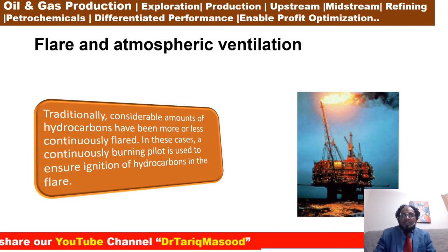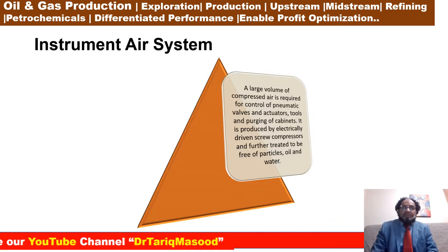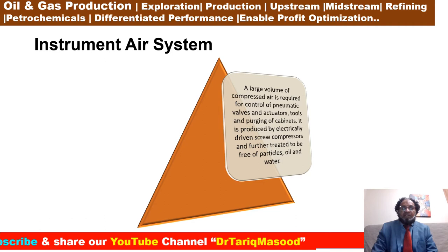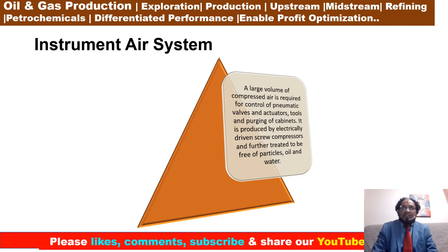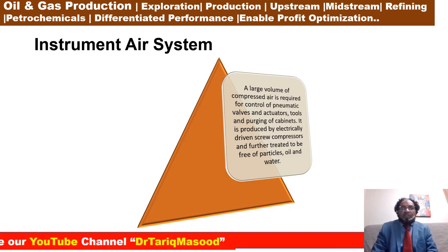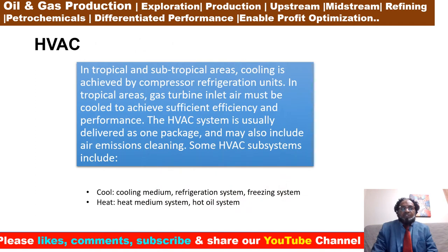Okay, from the next slide, we'll discuss the instrument air system. Instrument air system: a large volume of compressed air is required for control of pneumatic valves and actuators, tools and purging of cabinets. It is produced by electrically driven screw compressors and further treated to be free of particles, oil and water content. Okay, so HVAC system.